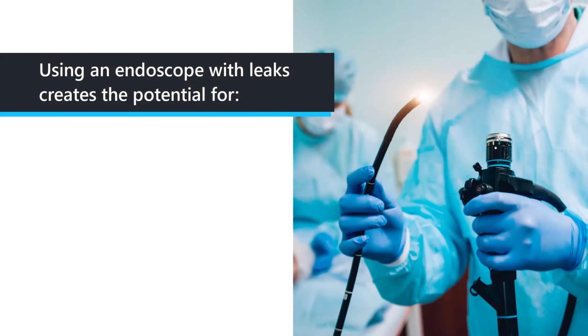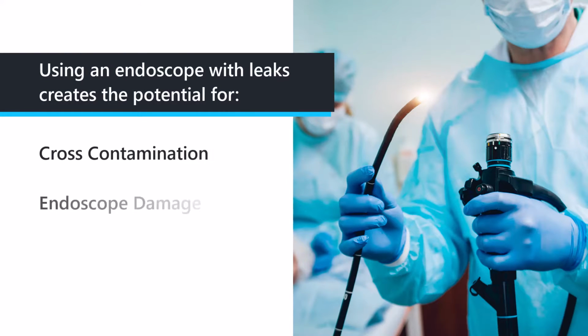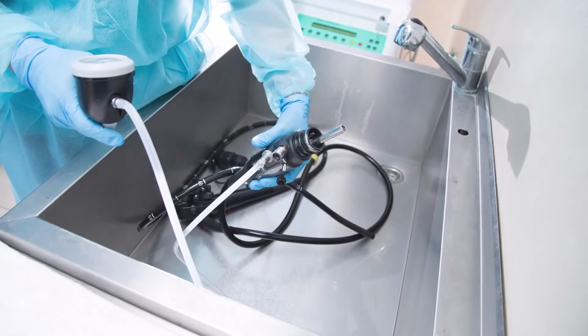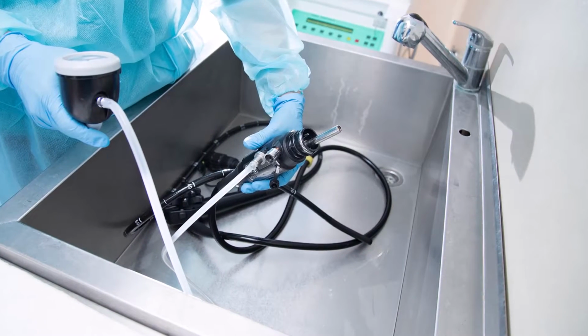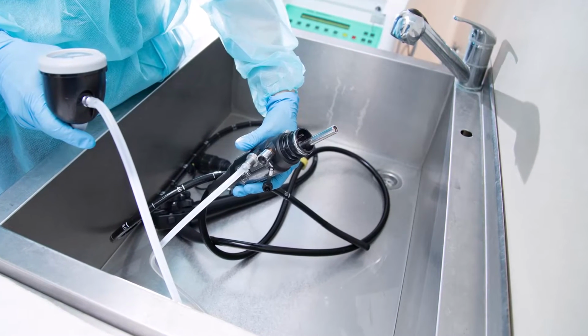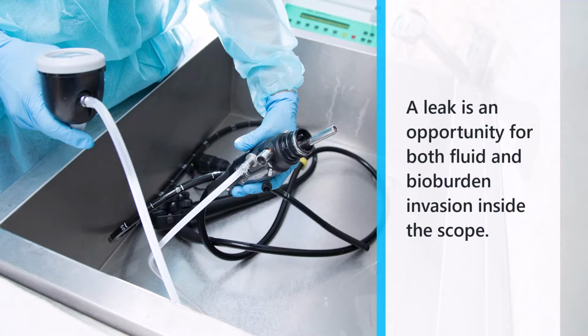Using an endoscope with leaks creates a potential for cross-contamination, endoscope damage, and costly repairs. So it's important that we test and measure to make sure that we're discovering leaks, no matter how large or small. Leak testing is performed every time a scope is processed, before immersion in any fluid. A leak is an opportunity for both fluid and bioburden invasion inside the scope.